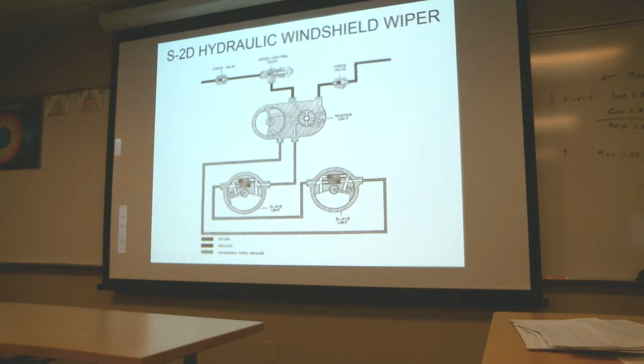Check valves are sometimes installed in the circuit in order to prevent back pressure from influencing the operation of these devices. And also, you might find integral relief valves that are installed in the motors. If the blades are restrained for any reason, it prevents the actuator, or the motor in this case, from damaging itself. So it relieves fluid to prevent that from happening.